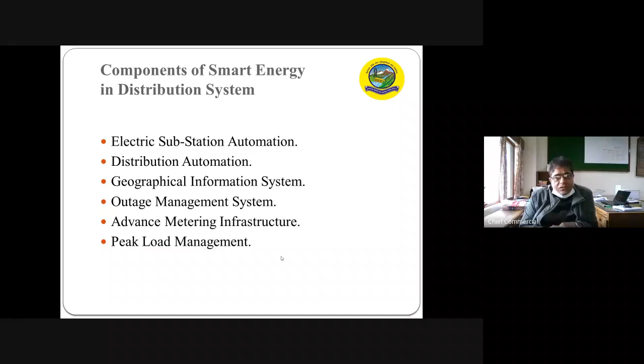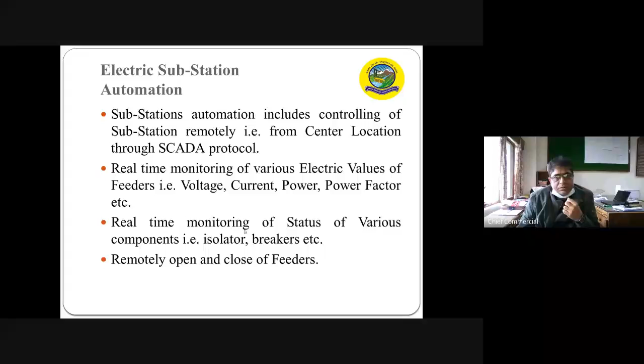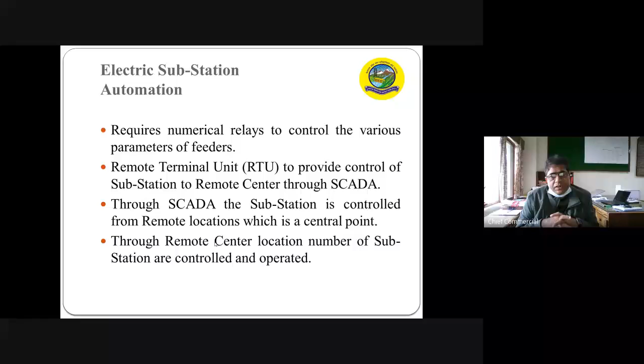We talk of electrical substation automation. It includes controlling the substation remotely from a central location through the SCADA protocol, real-time monitoring of various parameters such as voltage, current, power, and power factor, real-time monitoring of the status of various components such as isolators, breakers, fault passage indicators, sectionalizers, auto reclosers, etc., and remotely opening and closing the feeders. This requires numerical relays to control the various parameters of feeders, and remote terminal units to provide control of the substation to the remote center through SCADA. Through SCADA, the substation is controlled from a remote location, which is a central point. Through the remote control center, a number of substations are controlled and operated.